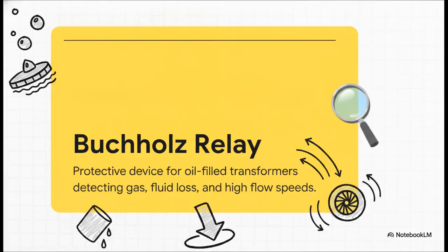To put it simply, this relay is essentially a mechanical first responder. It doesn't rely on fancy microchips to do its primary job. Instead, it uses the physical principles of buoyancy and fluid dynamics. Believe it or not, the underlying physics are surprisingly similar to the float in your toilet tank, except scaled up to protect multi-million-dollar electrical grids from three major fault conditions: dangerous gas accumulation, a severe loss of insulating fluid, and excessively high fluid flow speeds.